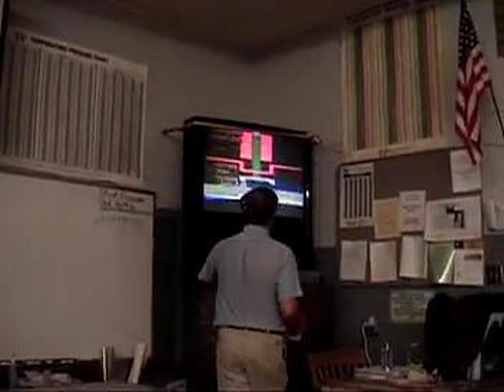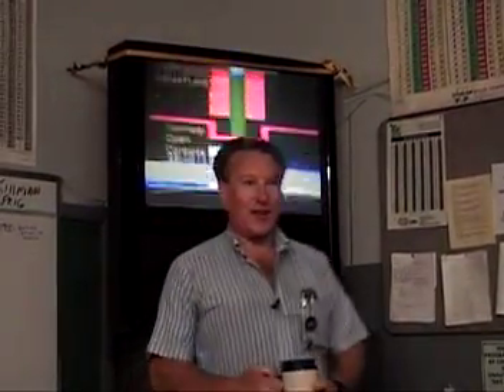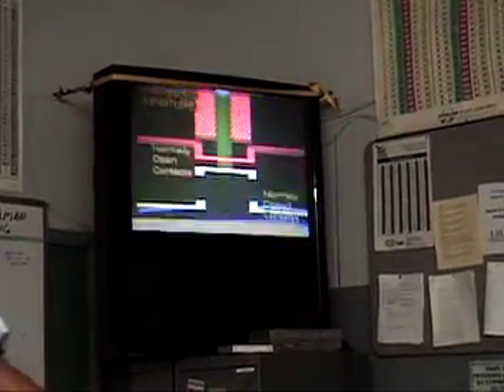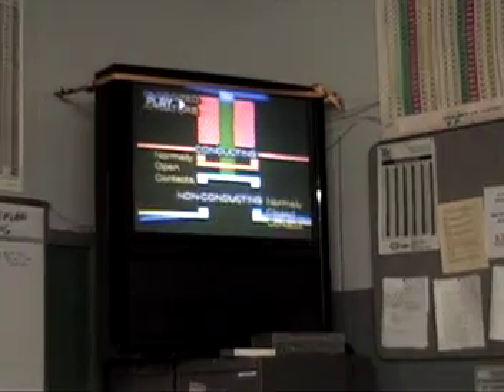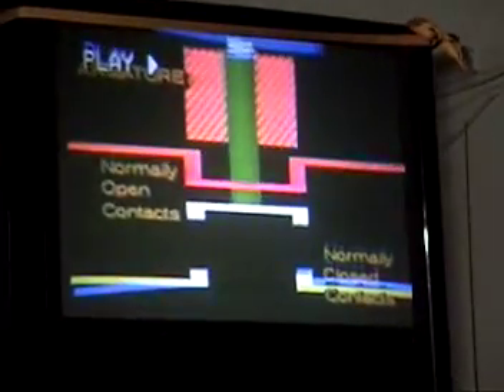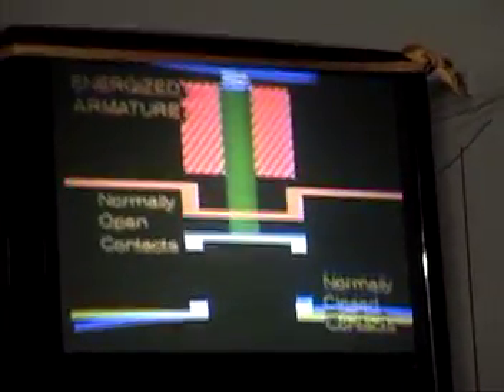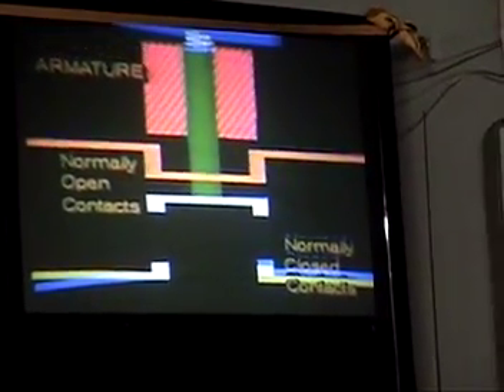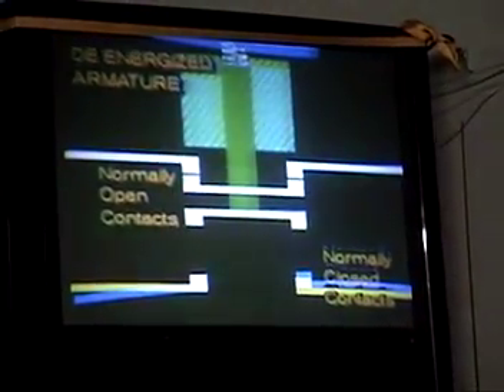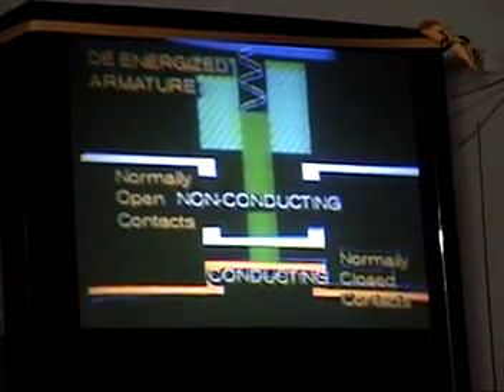Now some of them close one set of contacts, open another set of contacts. Like on here, see where it says normally closed? Those open. See where it says normally open? Those close. Okay, so that's the way a fan relay works. Or normally closed contacts. Both types are shown here. This condition is maintained until the energizing voltage is removed. Then the contacts return to their normal position.